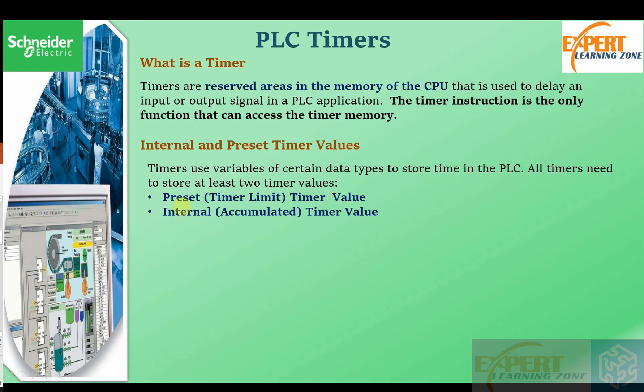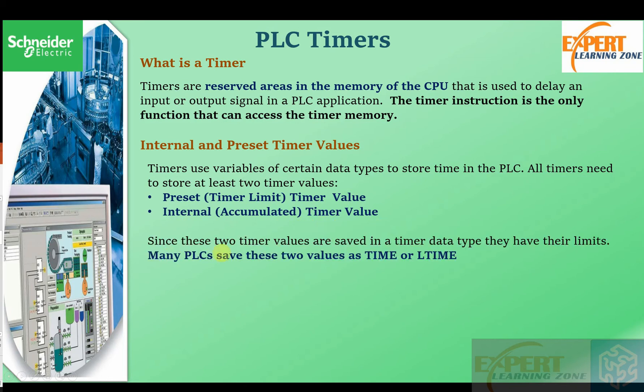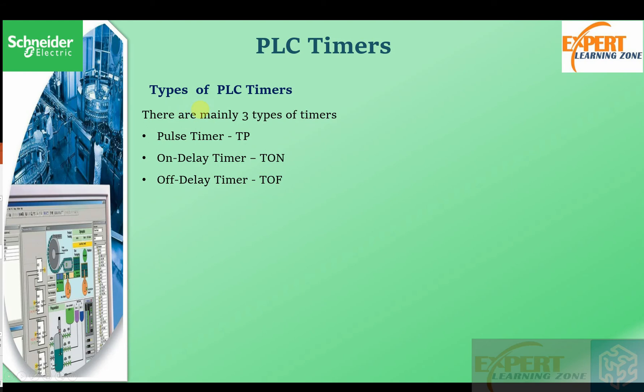Timers use variables of certain data types to store time in the PLC. All timers need to store at least two values: the preset or timer limit value, and the internal or accumulated timer value. Since these two values are saved in a timer data type, many PLCs save them as TIME or LONG TIME. However, the maximum and minimum preset and accumulated values depend on the data type of the timer variable and can change from one brand of PLC to another, or even between different series of the same brand. Check the programming guide for exact details.